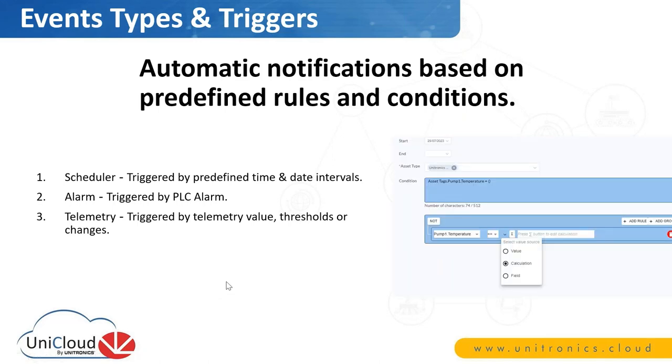In order to set up the alarm or the events, we have a very simple, very robust, very powerful rules and condition mechanism, where you can add more and more rules, group them, and decide which group will be considered first. And you can calculate, using the rule over here, for example, by a value. For example, if temperature of pump one is above a certain value, like 90 degrees, or another tag.